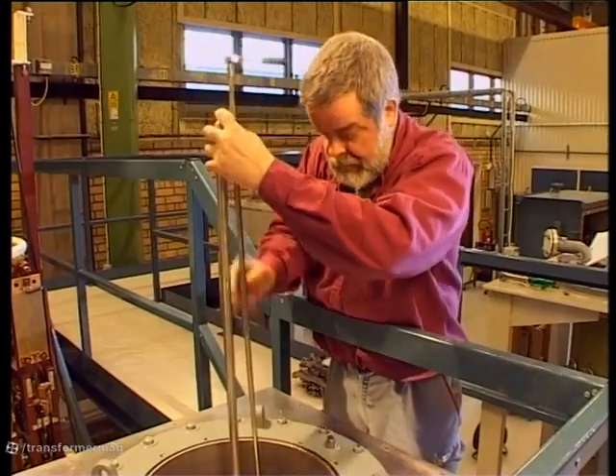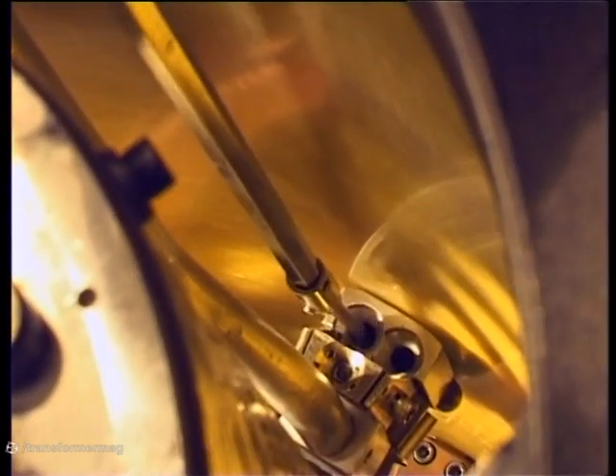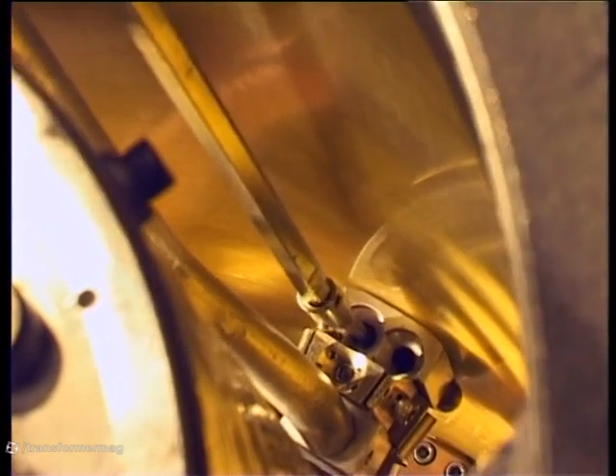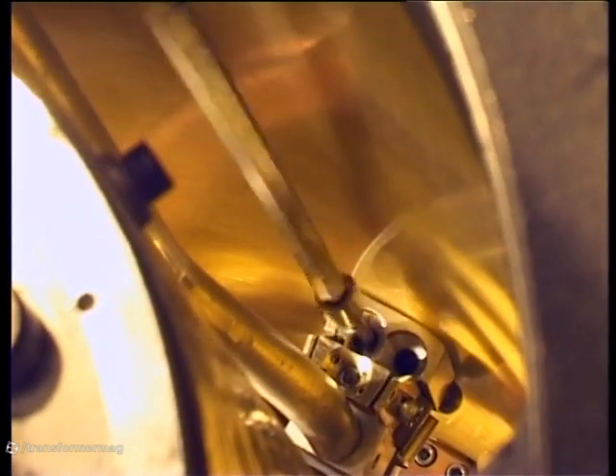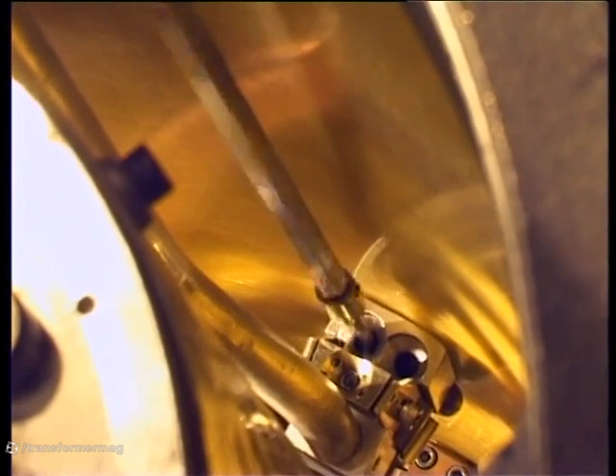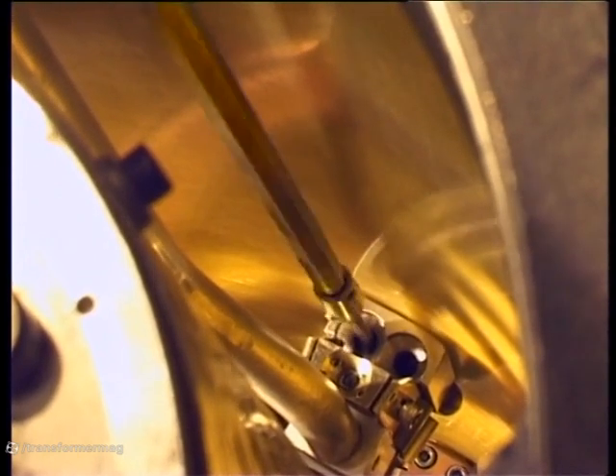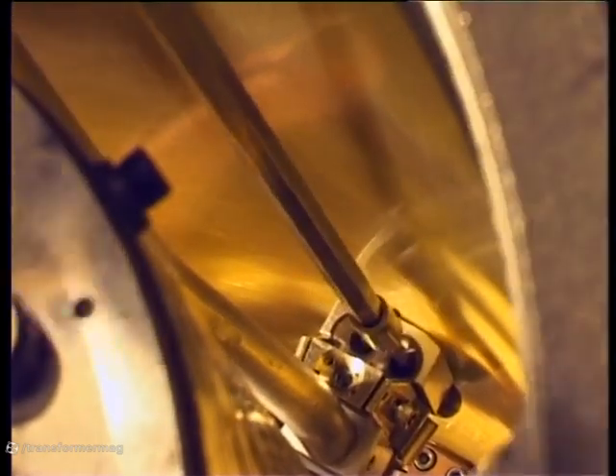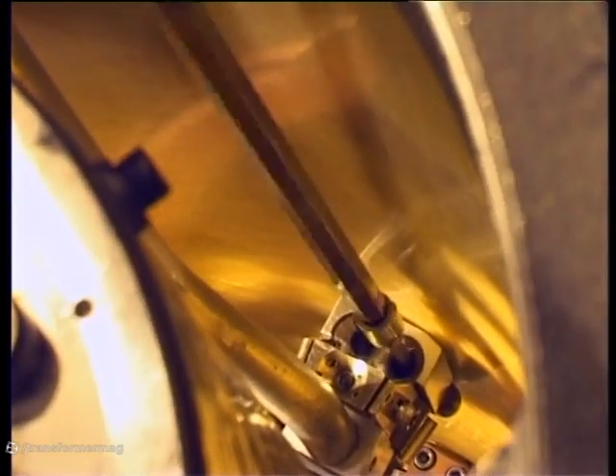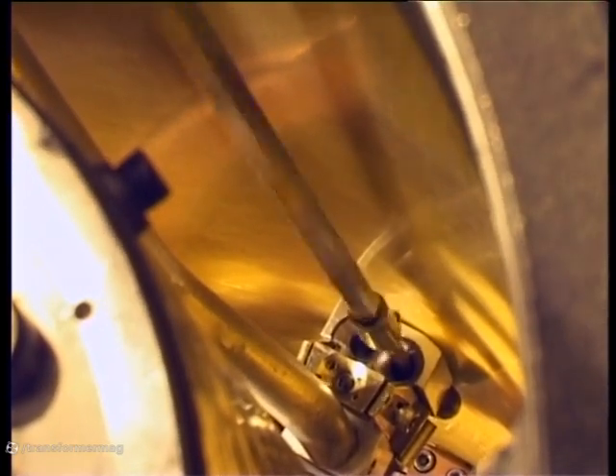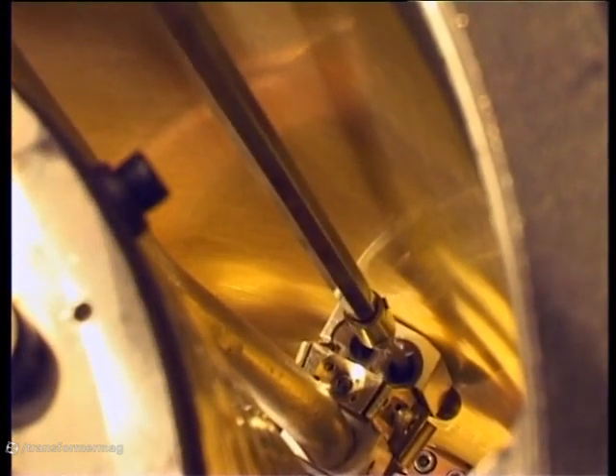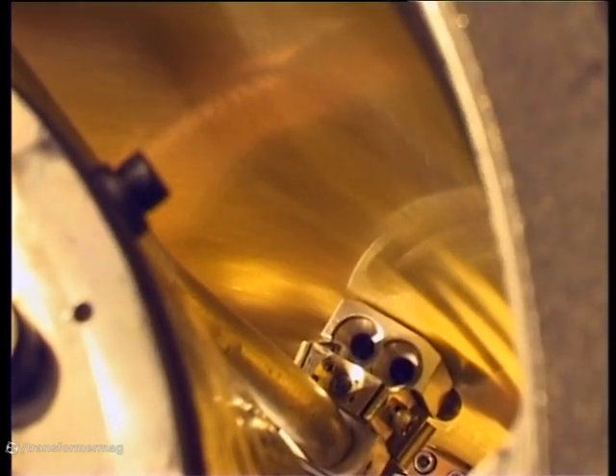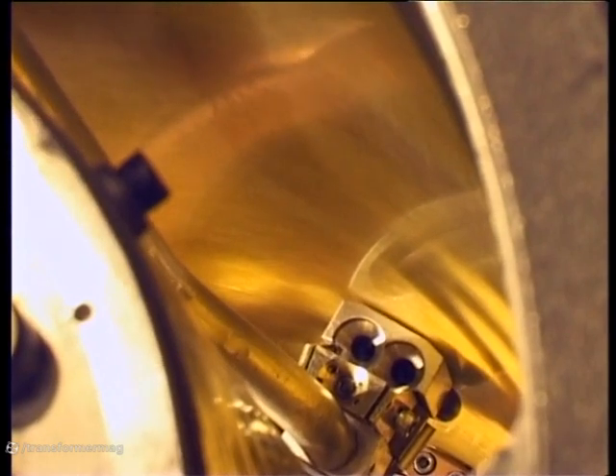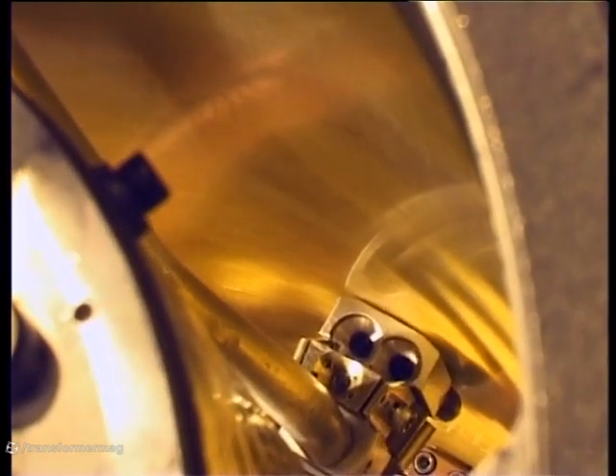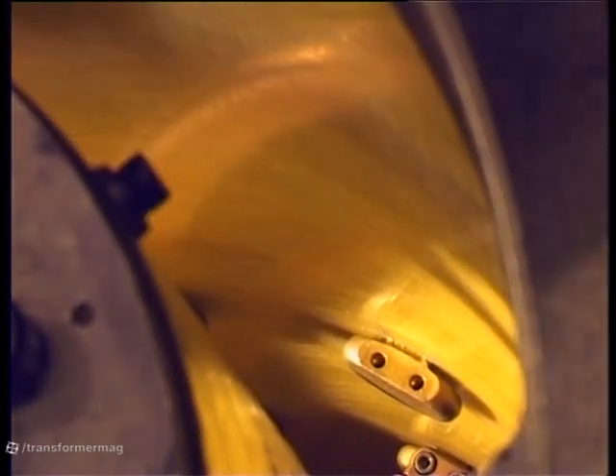Unscrew the two M6 screws with the screwing tool. We recommend unscrewing the screws alternately. Unscrew the first screw 5 turns, then unscrew the second screw fully by 12 turns, and finally unscrew the first screw fully by a further 8 turns. The screws are captive in the contact holder, so there's no risk of them falling out of the tool. Do the same with the two blades in the two lower phases.